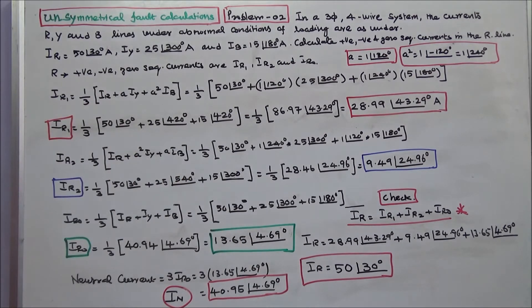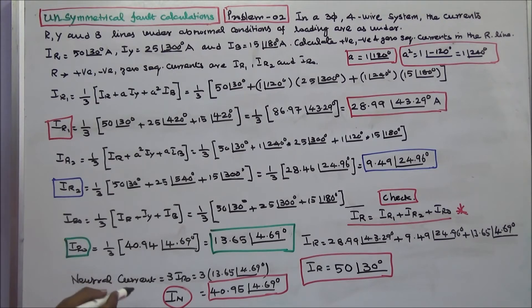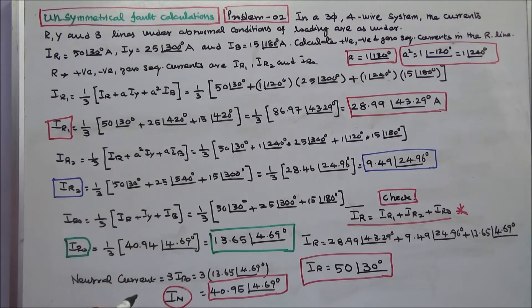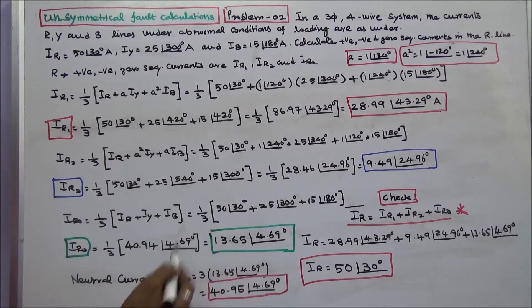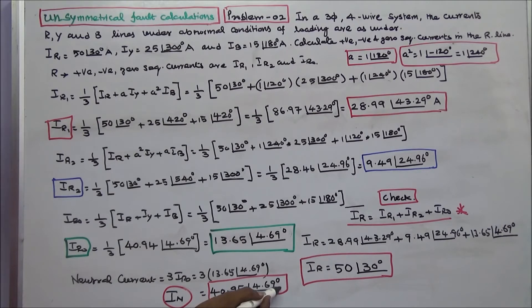Next, we calculate the neutral current. Neutral current is equal to IR plus IY plus IB, or 3 times the zero sequence current. So 3 × 13.65 angle 4.69 degrees equals 40.95 angle 4.69 degrees. This is the neutral current.